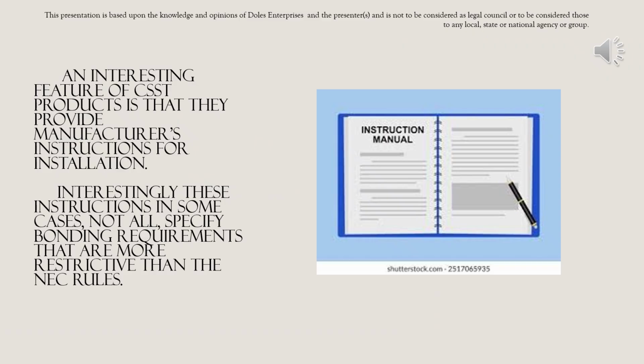One of the interesting features about the CSST piping is that it does specifically require that it has to be installed per manufacturer's installation instructions. There's all kinds of criteria. So every system has a little bit different way of being used. What you get training on one brand of CSST piping may not apply to all. A good example is we got yellow jacketed CSST, we got black jacketed, and some say the black jacketed CSST doesn't require a bond in quite the same way.